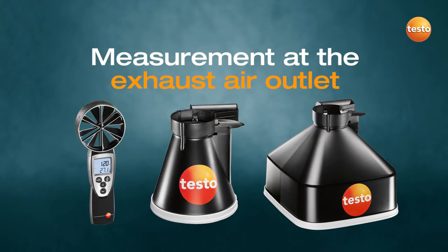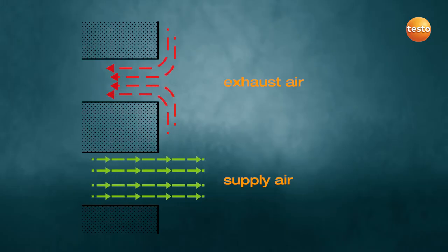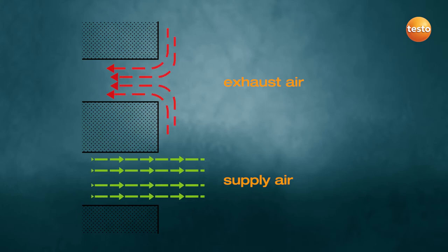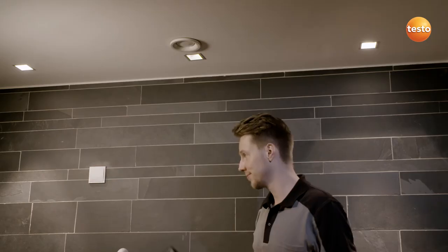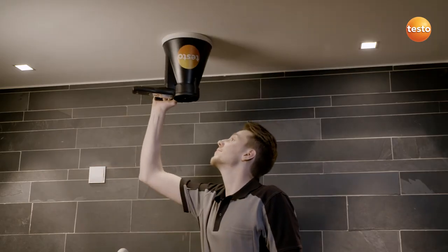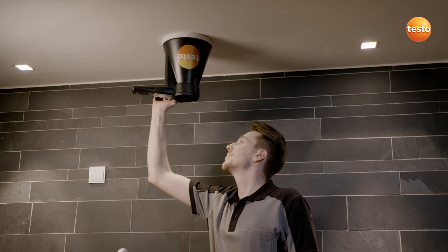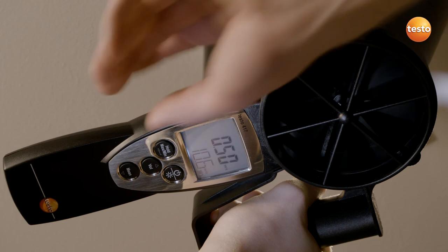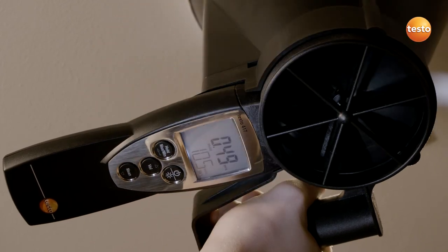This is how you measure properly at the exhaust air outlet. A funnel is required to measure the exhaust air. There is no directed flow profile available for exhaust air as the air is sucked in funnel-like from the room, meaning there is no definable area in the room via which the volume flow can be determined. This challenge is easily solved with the Testo 417 funnel, because it creates defined flow conditions at some distance from the plate outlet in a fixed cross section.